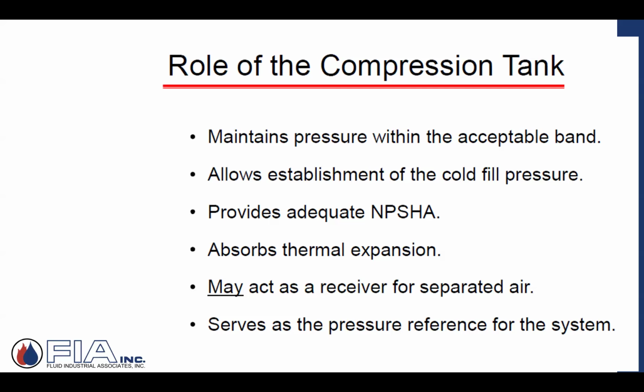So I have a responsibility of this tank to keep the system pressure within a high and a low. Establish a minimum cold fill. We'll talk more about that. NPSHA, we'll get into NPSH, net positive suction head, what that means later on. Thermal expansion, everyone kind of grabs that. Yeah, as we heat the water, it expands. I've got to have a place to have that expansion take place. May act as an air separator. We'll talk about that. And as we get into the point of no pressure change, pump location serves as the pressure reference for the system.